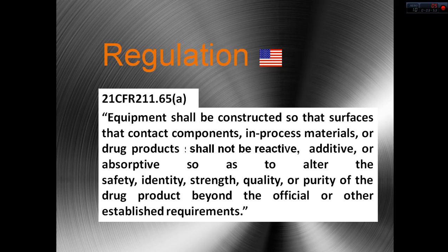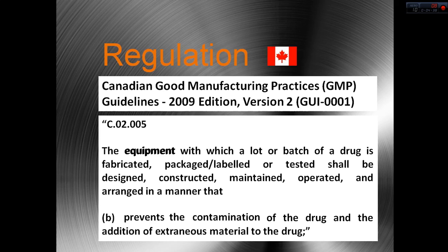Regarding regulation, we are not going to find the word 'passivation' in the Good Manufacturing Practices, but what we are going to find is a paragraph requiring that the equipment — or the surface of that equipment — should not be reactive. It's quite clear that if there was iron oxide, there was some kind of reaction. In Canada, the Food and Drugs Act requires that drugs should be prepared in sanitary conditions, and there are no sanitary conditions on a surface with iron oxide. In other words, the equipment should prevent contamination, and that surface should be inert and passivated if we don't want to contaminate our products with iron oxide.